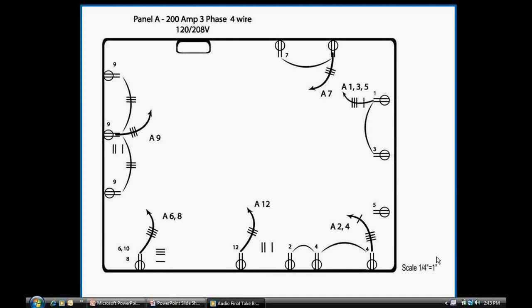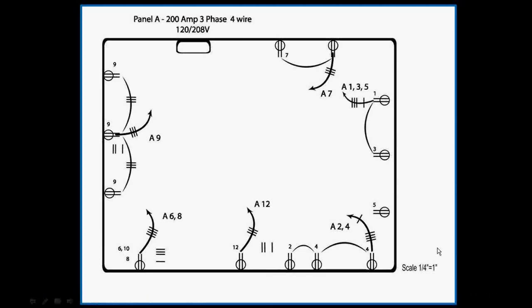Next, I would measure the MC cable. Let's say that the conduit feeding from outlet to outlet on this drawing is MC cable. You roll it off the same as EMT conduit. You roll off all the 12-2 MC cable, then all the 12-3, 12-4, and so on. You write the total length on the material take-off sheet as well, showing the number of runs and application. Now again, I won't demonstrate doing the take-off for MC cable because I believe you have enough examples to do that.